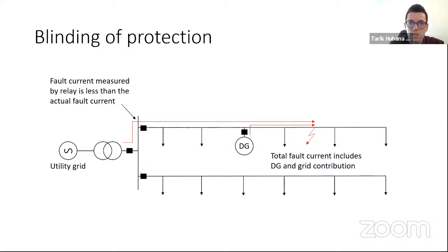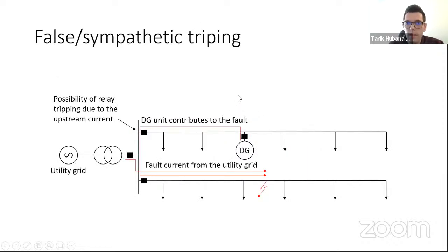So, blinding of protection. Here we can see a standard substation with 2 radial feeders. When you have a distributed generator installed in the system, in the case of a fault on the right side of this generator, both the generator and the main grid can contribute to the fault, and therefore it can lead to the blinding of the protection, where this fault relay measures a lower current than the actual fault current. Another problem is false or sympathetic tripping, because the distributed generator again contributes to the fault, and the fault current flows both from the utility grid and from the distributed generator, and there is a possibility of a relay to trip due to the upstream current.